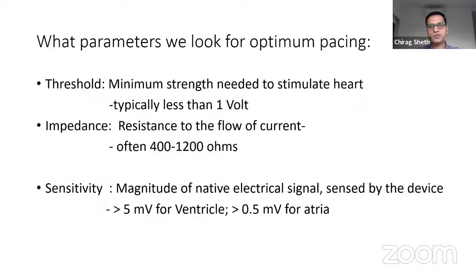So what parameters do we look for optimum pacing? We look for a threshold. That means what is the minimum strength needed to stimulate the heart, and typically it should be less than 1 volt. Second, we look for impedance, that is resistance to flow of the current, which is usually between 400 and 1200 ohms. And third, we look for sensitivity. That means what magnitude of electrical activity the lead is able to sense. So typically it should be more than 5 millivolt for the ventricle and more than 0.5 millivolt for the atrium.